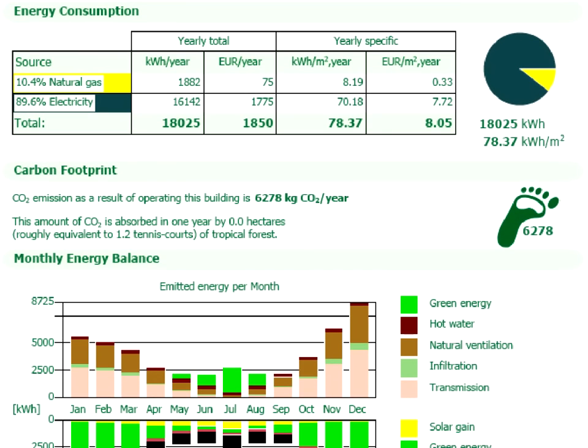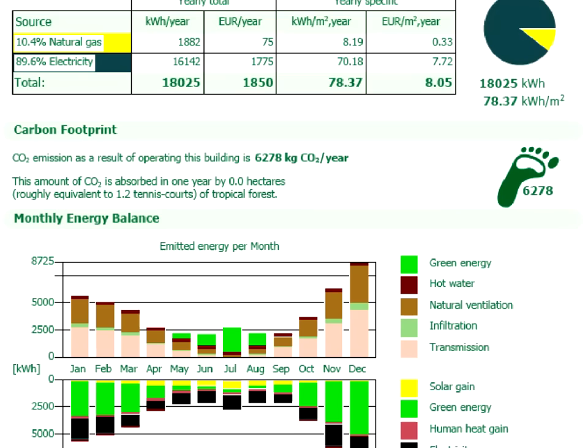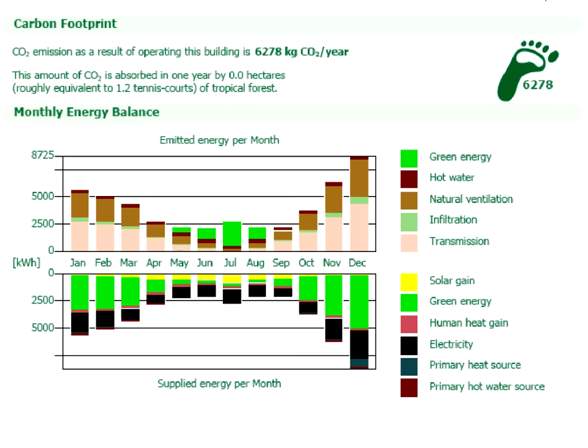The yearly total consumption is around 18,000 kWh. Remember that this value was over 54,000 kWh in the first design. The yearly total energy cost has been reduced from 3,000 Euros to 1,800 Euros — a savings of 1,200 Euros on energy in just one year. Any client would clearly understand this design argument. The yearly specific energy consumption is only 78 kWh per square meter now, compared to over 235 kWh per square meter in the previous design. The carbon footprint is close to 6,200 kg of CO2 per year, a huge reduction from the original 13,000 kg of CO2 per year.